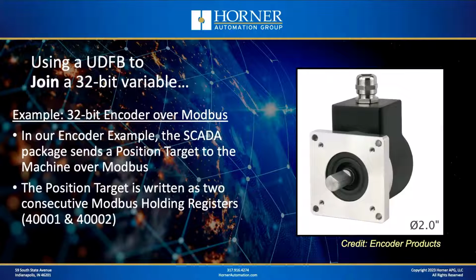Maybe in the same application, the SCADA package is writing a set point, a position target, let's say, that we need to monitor in the OCS that's coming in over Modbus. And again, it's going to be written by the SCADA package into 2 separate integer locations. Now, this time, because it's being written to the OCS, it's going to be stored in holding registers instead of input registers. Input registers are read-only, holding registers are read-write.